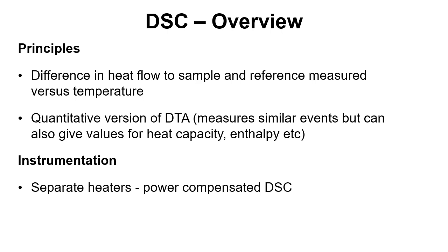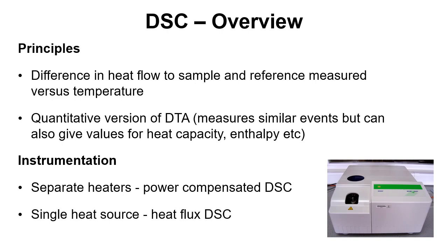For instrumentation, we can have separate heaters, which is referred to as a power compensated DSC, or we can have a single heat source, which is referred to as heat flux DSC. There is also a photograph of a DSC instrument shown.